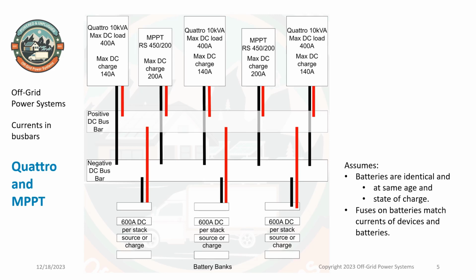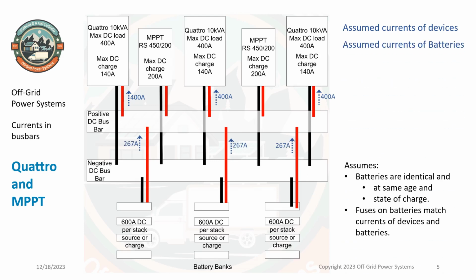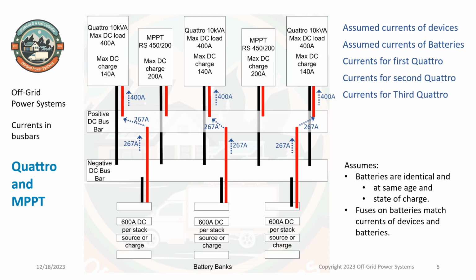What will happen if the MPPTs are supplying current? We'll start with the Quattros requiring load currents. When the batteries supply 267 amps each, later we'll show that the MPPTs' currents will make up the deficit. The left Quattro is supplied by the left battery, the middle Quattro is supplied by the middle battery, the right Quattro is supplied by the right battery, but the Quattros still don't have enough current to supply them.